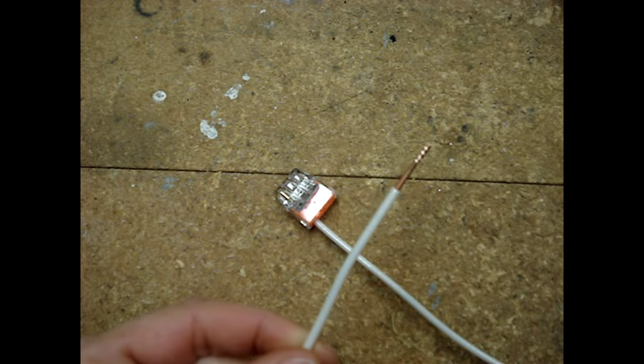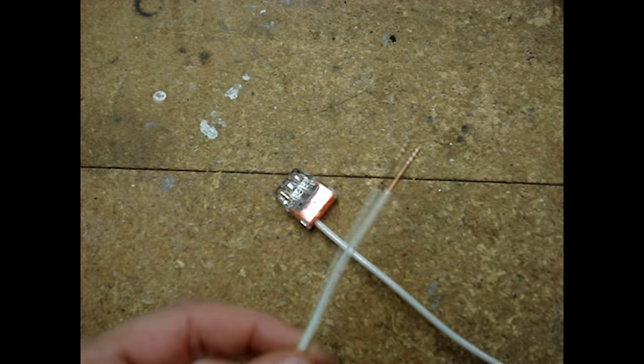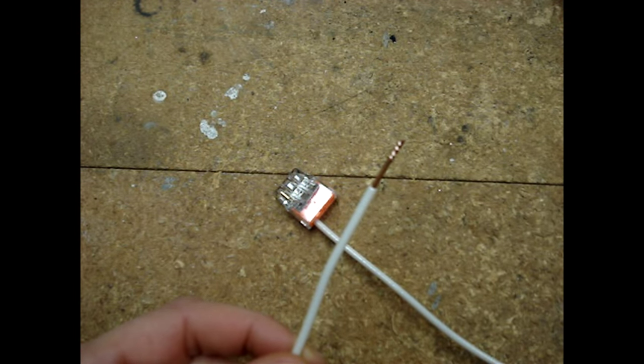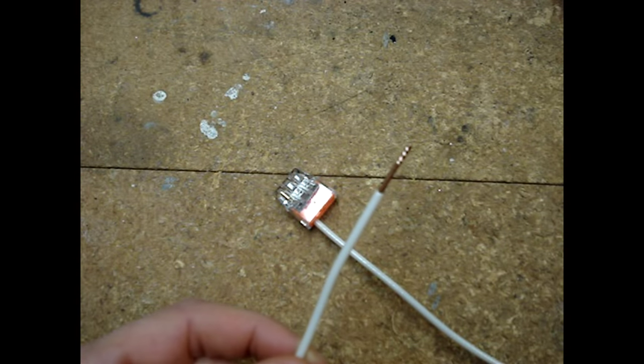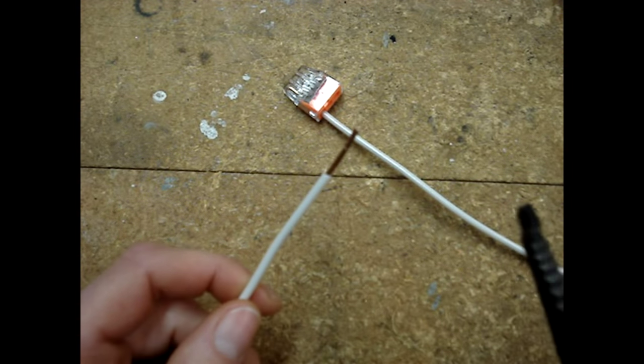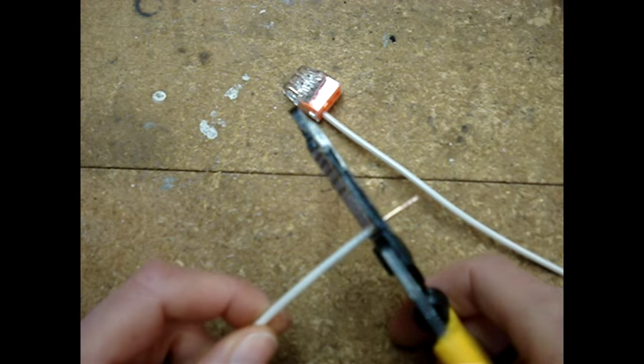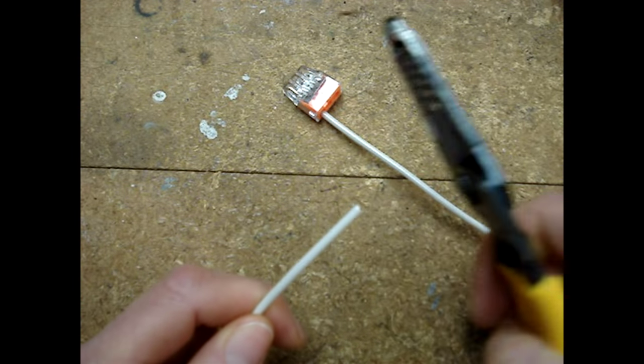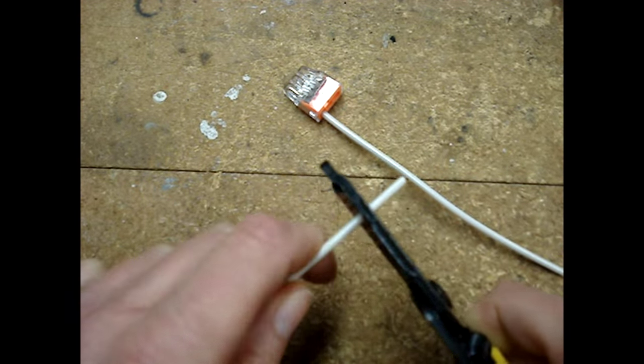They're only reusable with solid wire. It must be the same gauge or smaller. So, for example, if you had a number 12 wire inserted into a port, you couldn't reuse that port and insert a number 14 wire. And if I wanted to reinsert this wire into the port, I would have to cut it back and then restrip it.